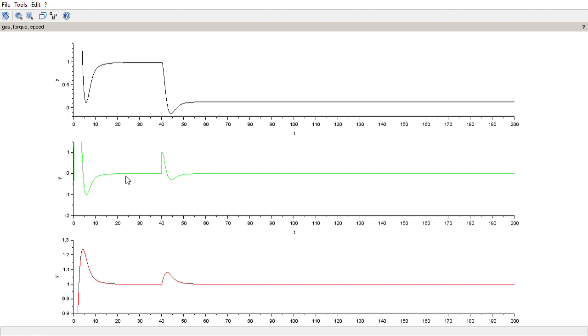So when you're at full load, your torque is balanced. So the torque here isn't the value of torque, it's the summation of the torque. And because speed isn't increasing, see speed here, there's no increasing, that means there was no excess torque. I was making enough torque to meet full load, but my gas was full open.